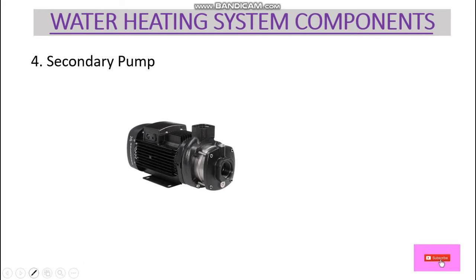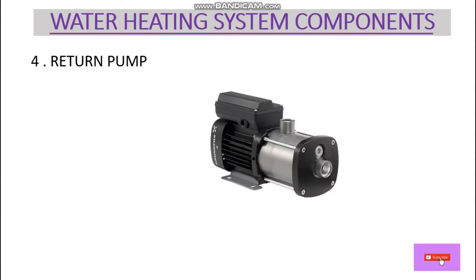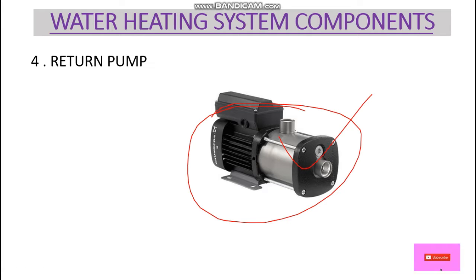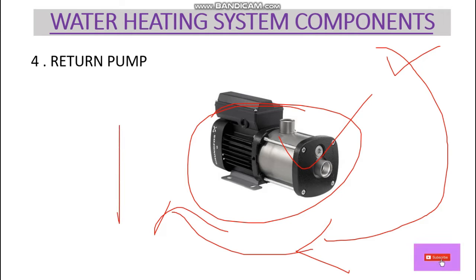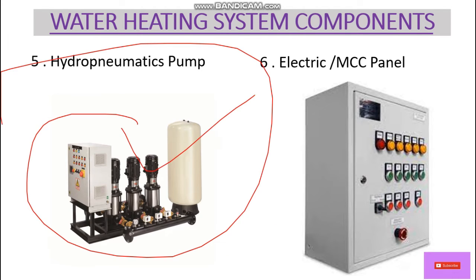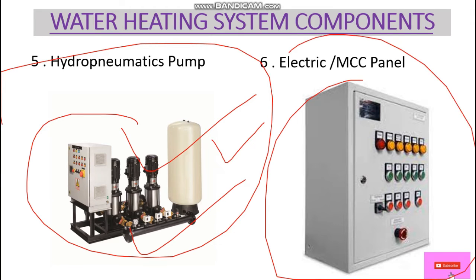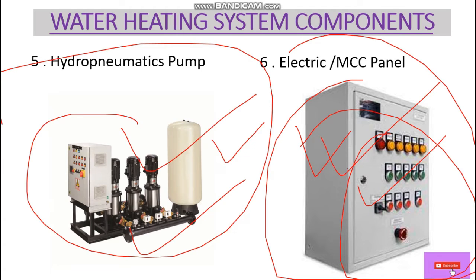The secondary pump helps circulate water from the PHE to the hot water mixing tank. The return pump helps to return the hot water from every fixture and feeds it back to the hot water mixing tank. The MCC panel — the electric panel — is where we can start and stop the heat pump, primary pump, secondary pump, and return pumps. These are the major components of the water heating system by PHE.